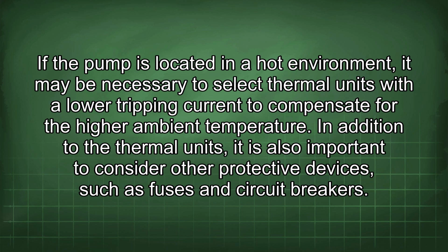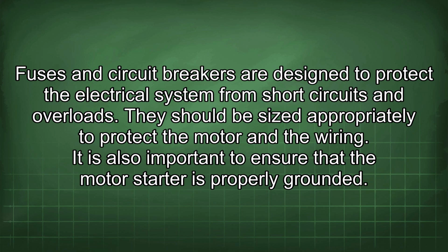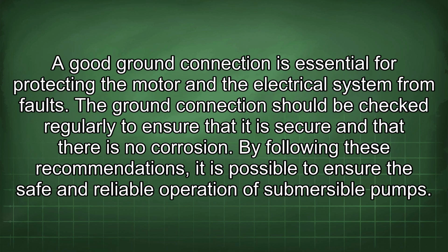In addition to the thermal units, it is also important to consider other protective devices, such as fuses and circuit breakers. Fuses and circuit breakers are designed to protect the electrical system from short circuits and overloads. They should be sized appropriately to protect the motor and the wiring. It is also important to ensure that the motor starter is properly grounded. A good ground connection is essential for protecting the motor and the electrical system from faults. The ground connection should be checked regularly to ensure that it is secure and that there is no corrosion.